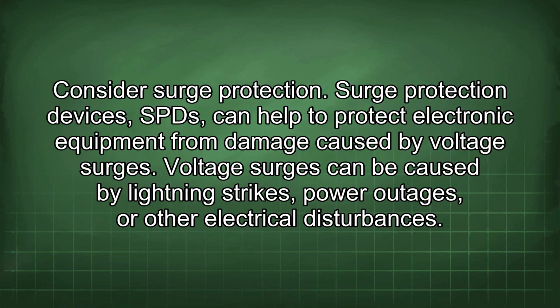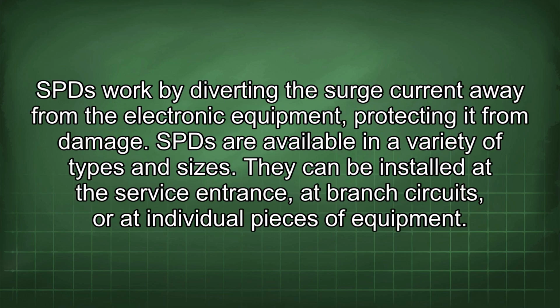Consider surge protection. Surge protection devices, SPDs, can help to protect electronic equipment from damage caused by voltage surges. Voltage surges can be caused by lightning strikes, power outages, or other electrical disturbances. SPDs work by diverting the surge current away from the electronic equipment, protecting it from damage. SPDs are available in a variety of types and sizes. They can be installed at the service entrance, at branch circuits, or at individual pieces of equipment.